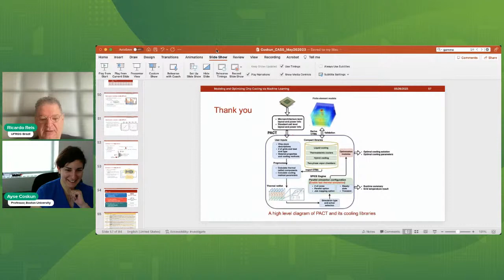But I have one: for all these cooling systems using water or other liquids, how big is the cooling system? That's a great question. For liquid cooling, the traditional way would be to have microchannel cooling on the chip or on the package, though sometimes you don't need microchannel. You connect this to a pump that's physically sizable, typically one pump per rack in a data center. The pump pushes the liquid, and you collect it back into the pump. That's the typical liquid cooling scheme.